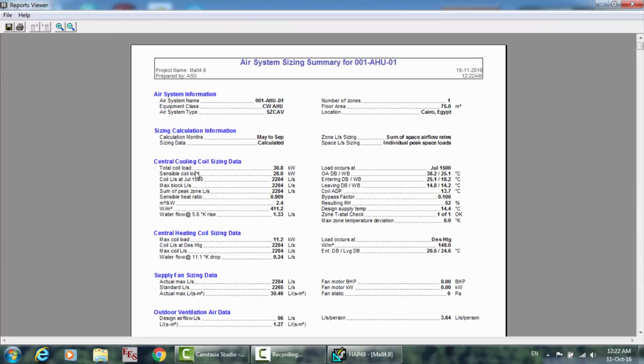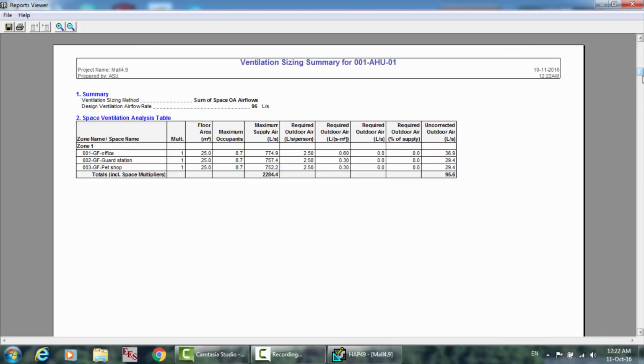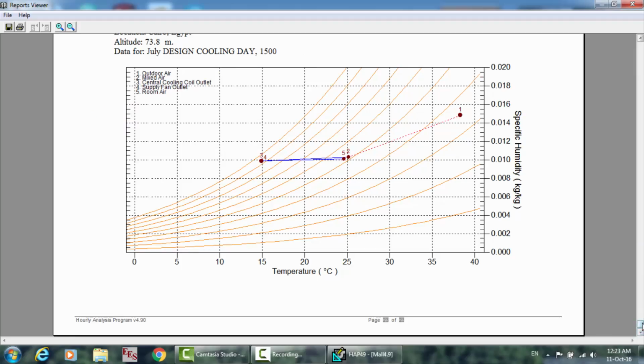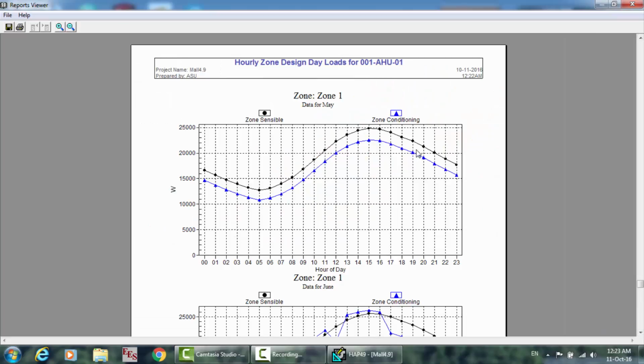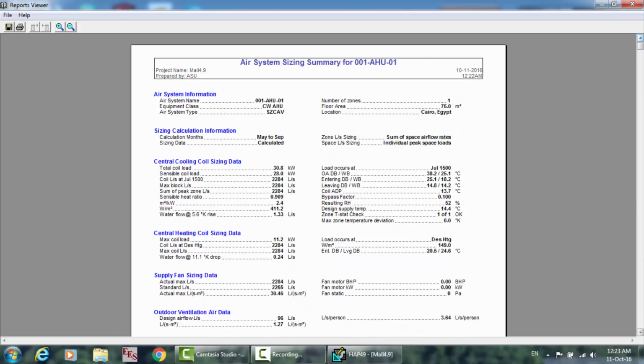Oh, notice that the total coil load increased. Here it becomes 30.8 kilowatts. This is due to considering the cooling load from 0 to 23 clock. But you will also find here the complete curve, and for this HAP takes into consideration from 0 to 23 that we need the HVAC system. The HVAC system will run around the entire day. Okay, notice this.